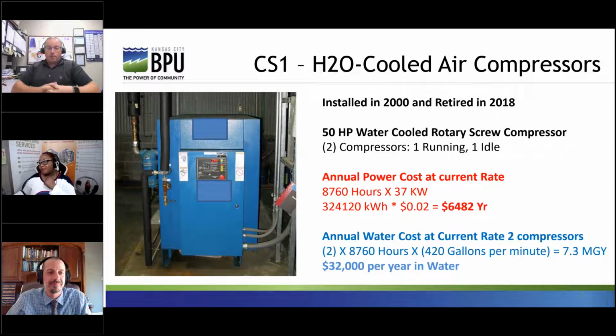The problems with these compressors were becoming excessive in 2016 and 2017. We were experiencing an increase in random failures, increases in iron and particle counts in oil samples. Vibration analysis indicated mechanical looseness in the wetted rotary screws. Cost of a new rotary screw would have been nearly half the cost of the compressor, and longer than a few days lead for most major repair parts.